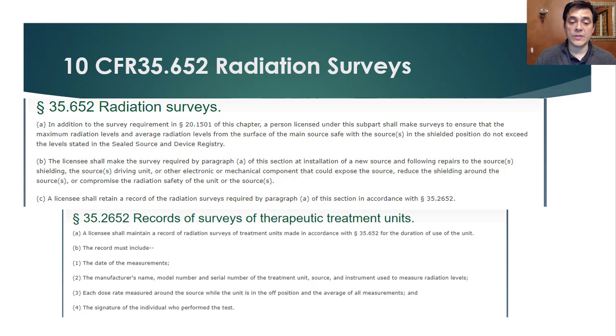So those records must include the date of the measurements, the manufacturer's name, model, serial number of the treatment unit source and instrument used to measure the radiation levels, and each dose rate measured around the source while the unit is in the off position, and the average of all the measurements, as well as the signature of the person performing the test.